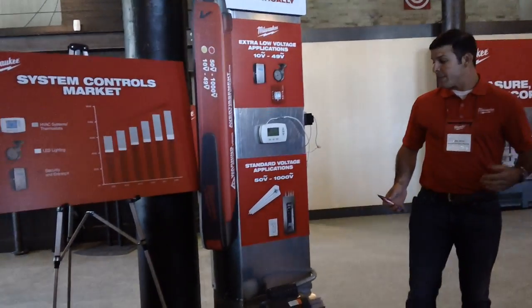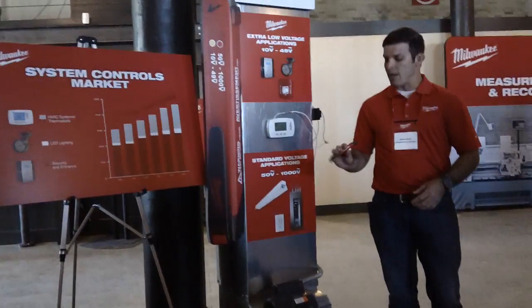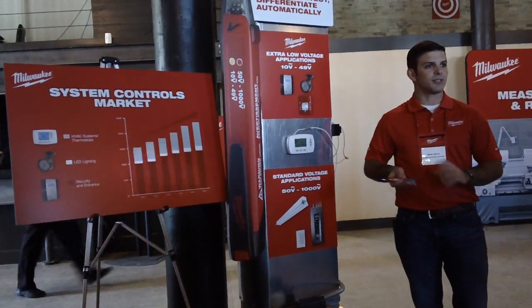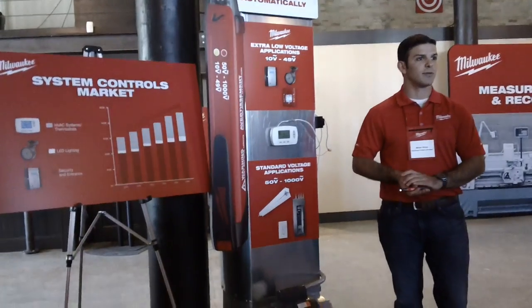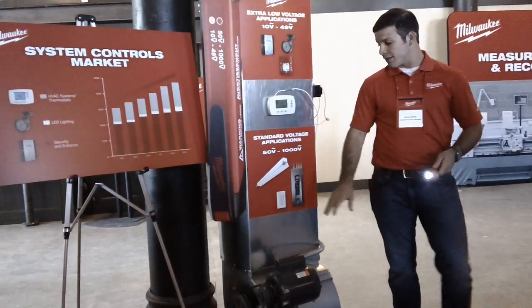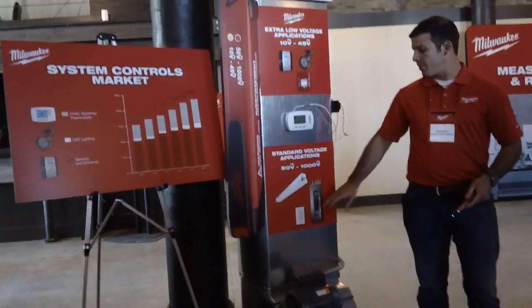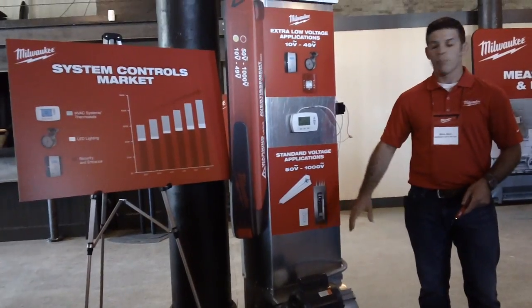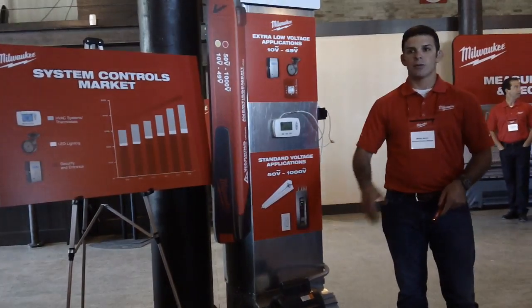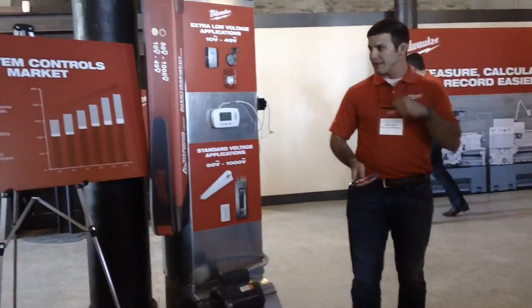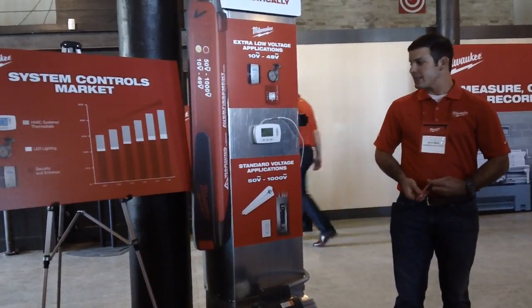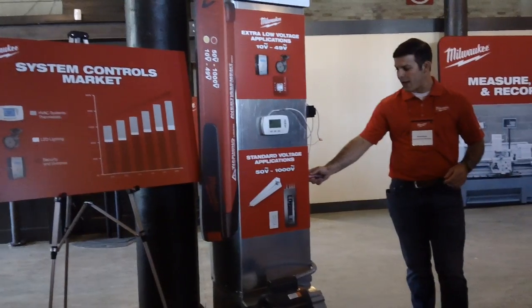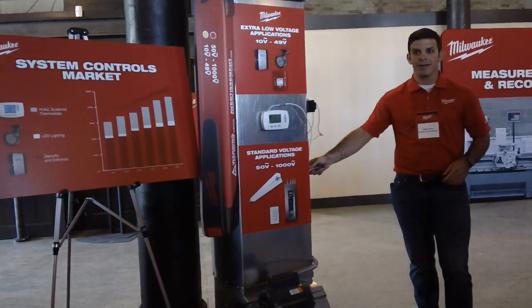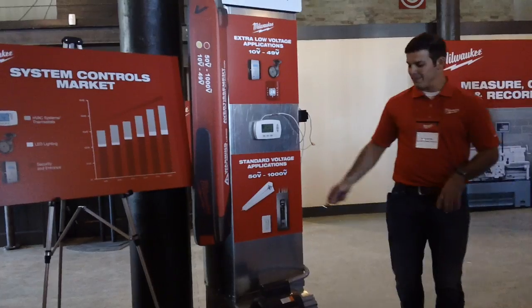So what they do is they detect voltage. Our standard non-contact voltage detector detects 50 to 1,000 volts AC. So that's going to be everything from electrical outlets, a lot of breakers, panels, motors, lighting, real common stuff that I see all over the place. But what we've seen recently, and I'll show you a demo, so this is just sort of how it works. If you put it near the wire, it'll flash red and start beeping.